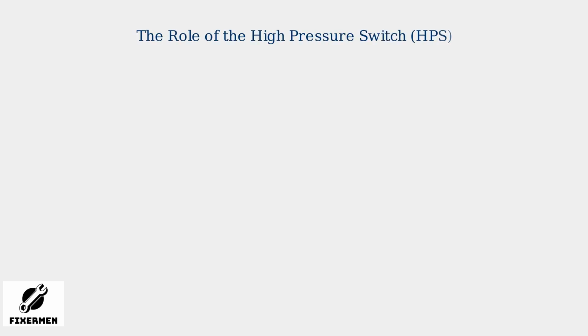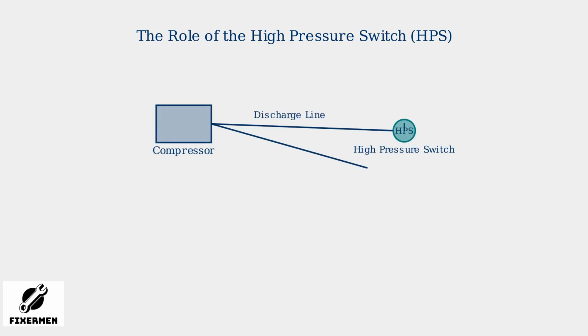The high-pressure switch, or HPS, plays a crucial safety role in Lennox HVAC systems by monitoring refrigerant pressure in the discharge line. Located between the compressor and the rest of the system, the HPS acts as a protective switch that prevents damage from excessive pressure. The HPS monitors pressure continuously. If pressure exceeds the safety threshold of 400 to 650 psi, depending on the model, the switch opens automatically.